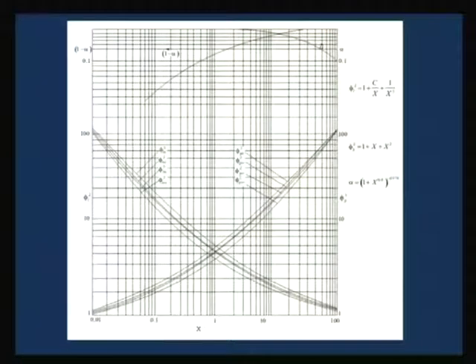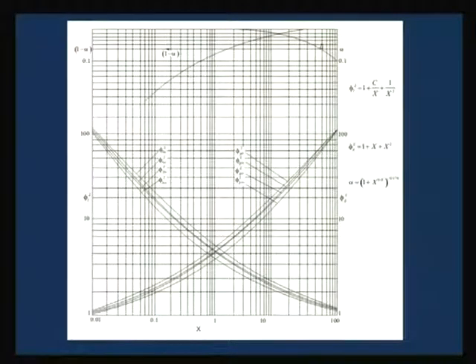To continue with our discussions on the improvements of the Lockhart-Martinelli correlations. Initially, the Lockhart-Martinelli correlation was applied for adiabatic two-phase two-component flow systems in horizontal pipes. After that, people noticed two things. First, looking at the graph plotted here, the curves are not smooth — they show a certain discontinuity of slope, and people thought this must be associated with a change of flow pattern, because with flow pattern change the pressure drop characteristics are bound to change since interfacial distributions are different for different flow patterns.